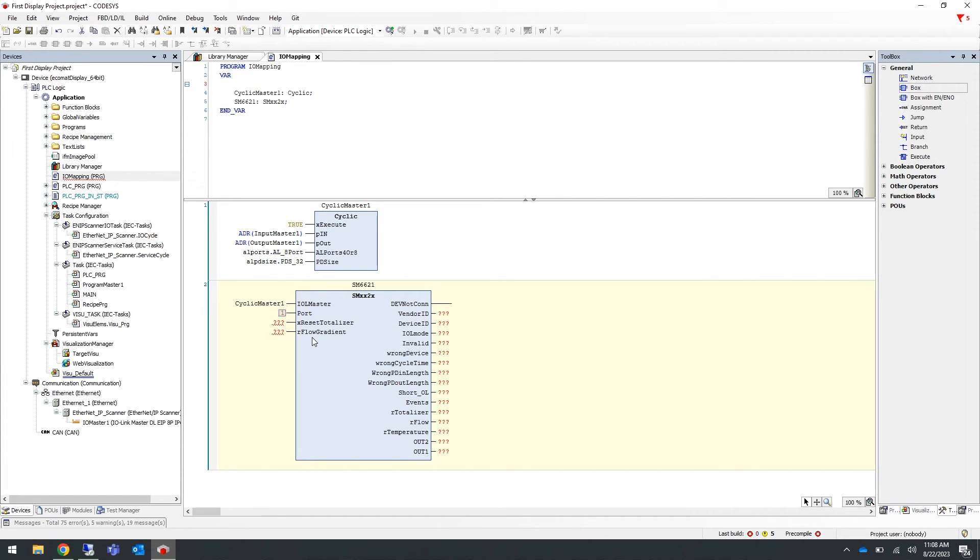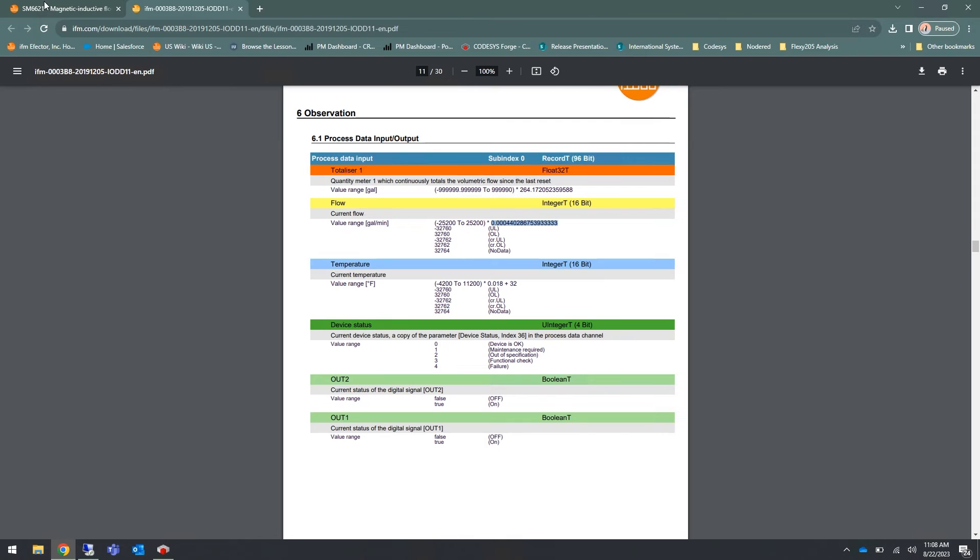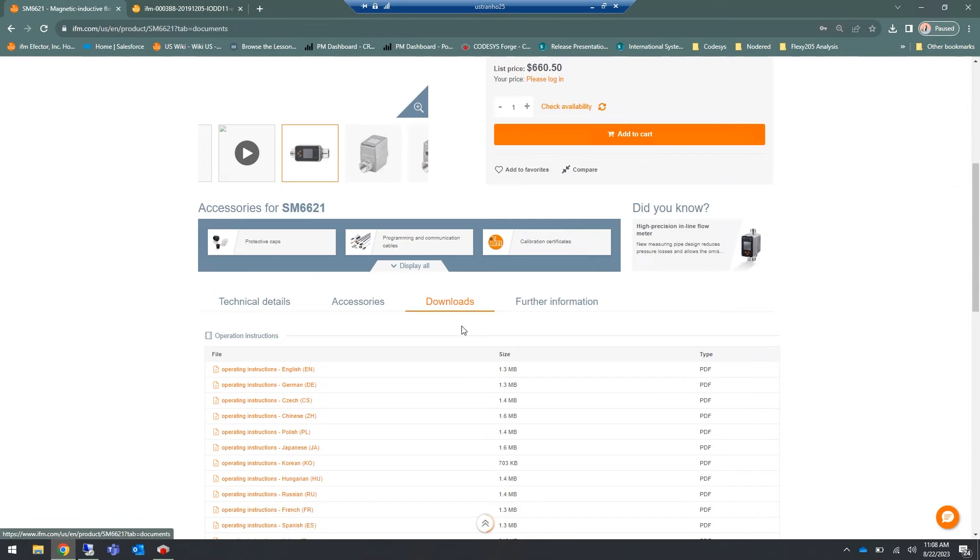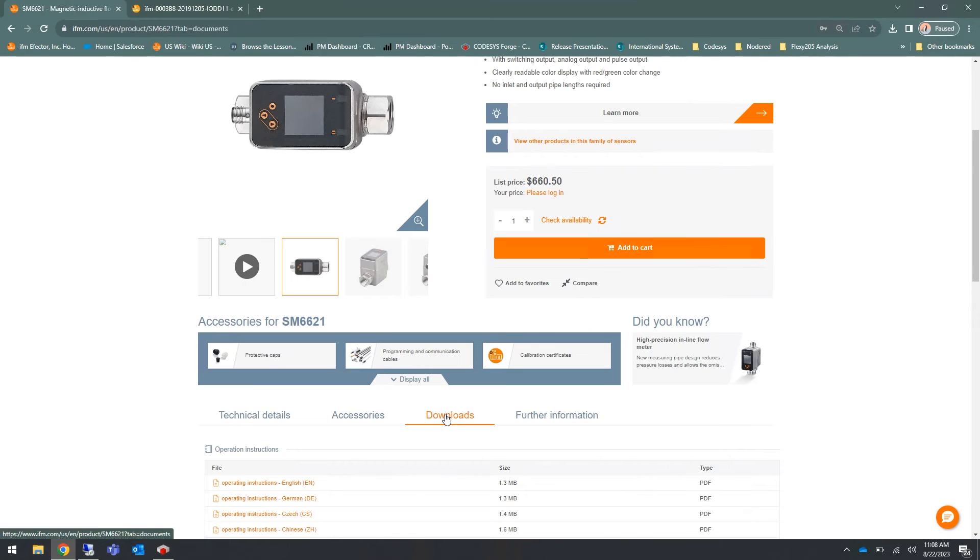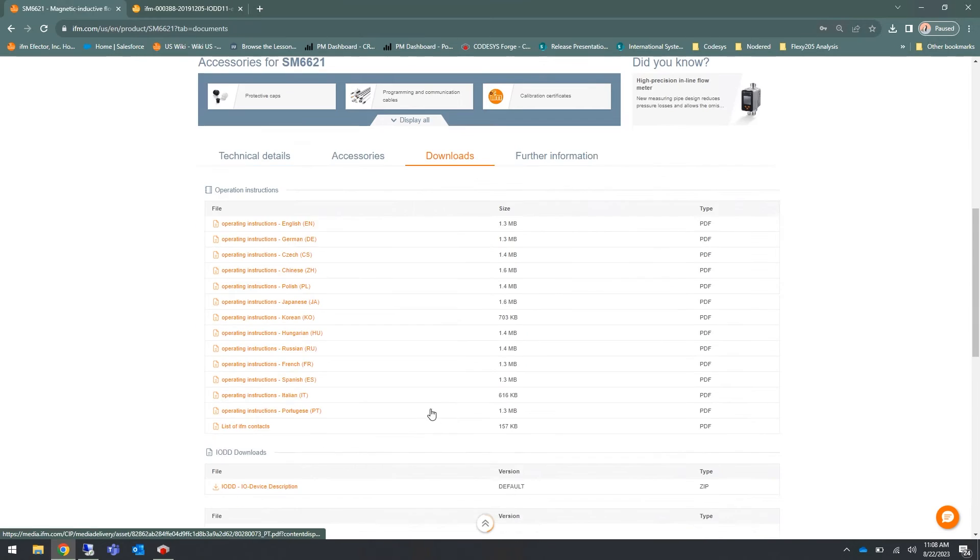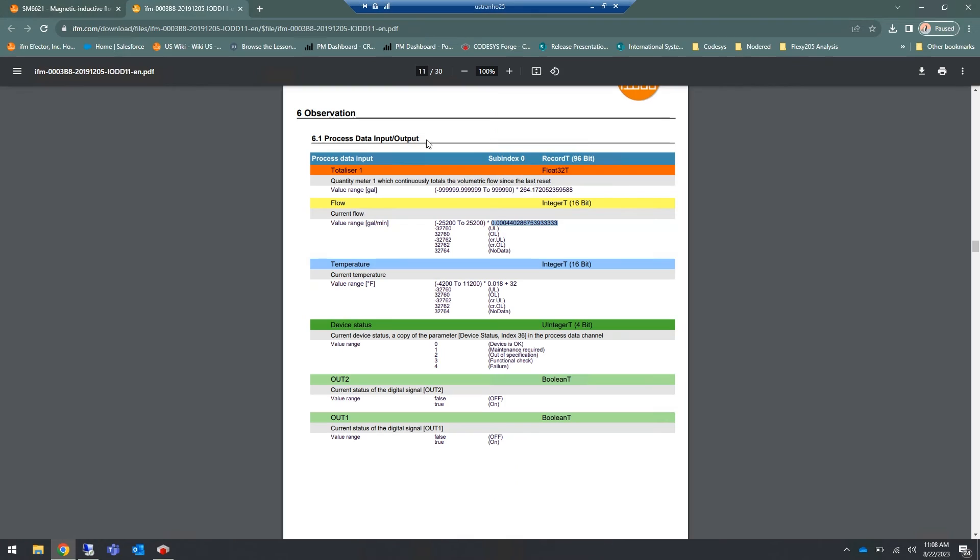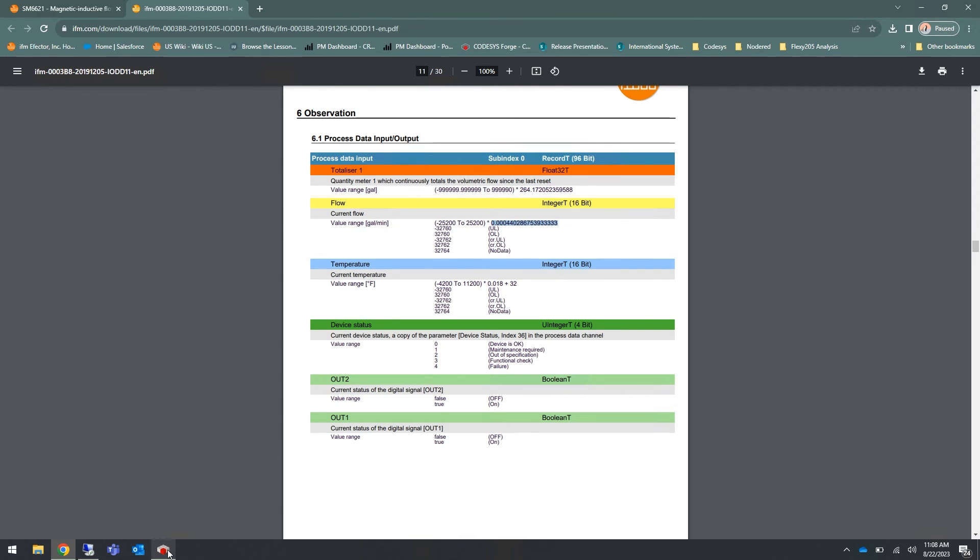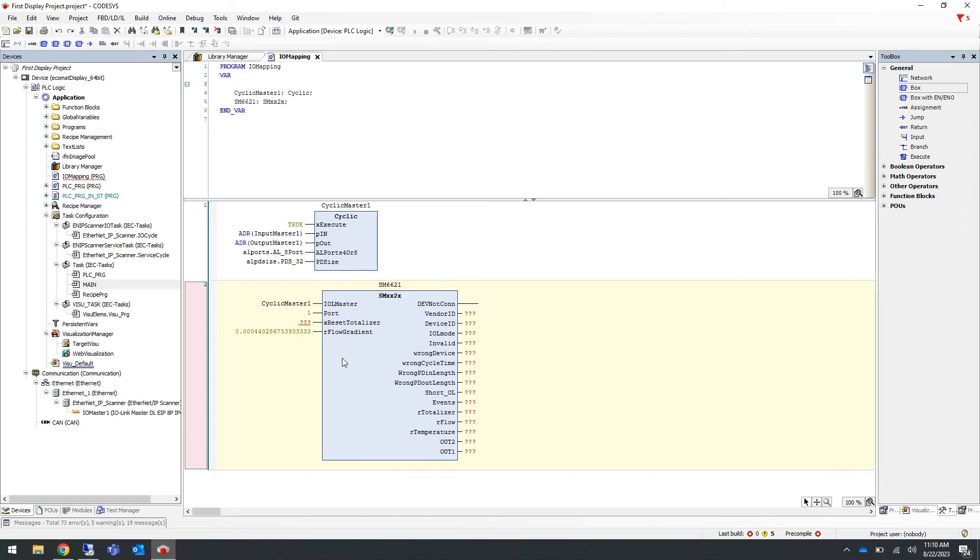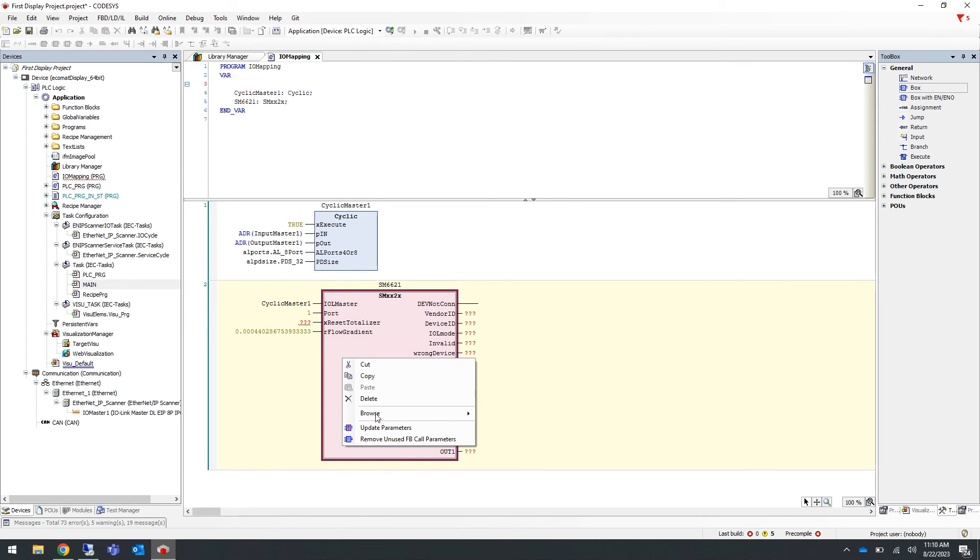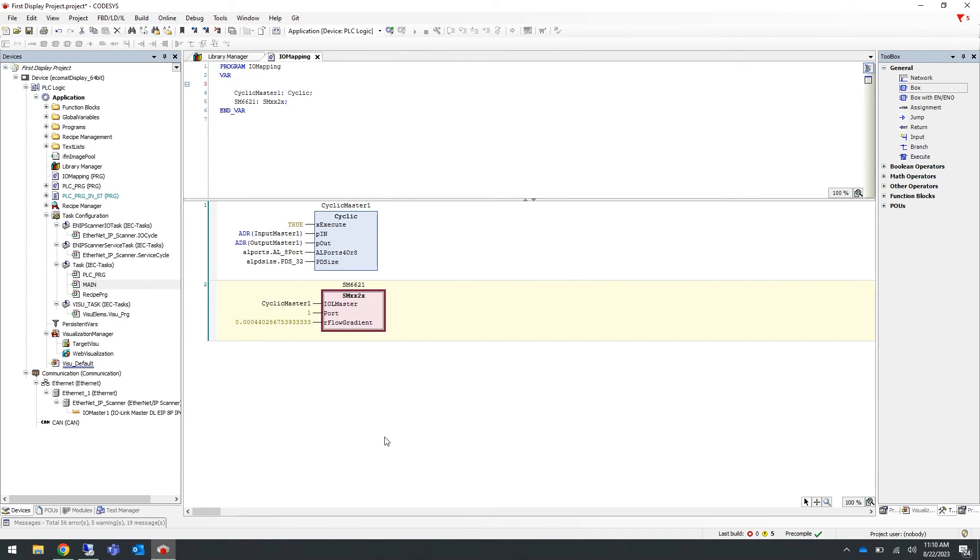You can find the flow gradient in the IODD PDF of our IO-Link sensors. For example, if we navigate to our website, on the SM6621 data sheet, go to the downloads tab and scroll down under IODD downloads and select the PDF. In the IODD PDF we will find the gradient for flow. Copy this and enter it into the flow gradient variable for the function block. Now right click and remove the unused function block call parameters.